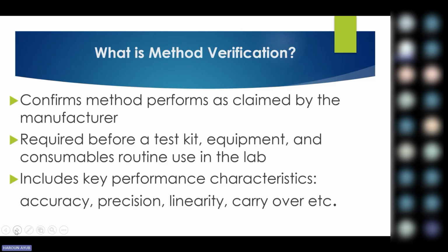In your laboratory's handbook or your user manual, you'll be able to get the carryover statistics, and you need to check if they conform to that. Whatever results you get, are they meeting the manufacturer's claim? In terms of carryover, we usually focus on the minimums of the values. It's never high; if it's high, it's a problem. When you have a high range of results run and then you run a sample, there is an issue. This carryover aspect also comes into play when we are doing linearity. When you're doing linearity studies, we usually subject the equipment to extreme high samples, and then we also run the extreme low samples.